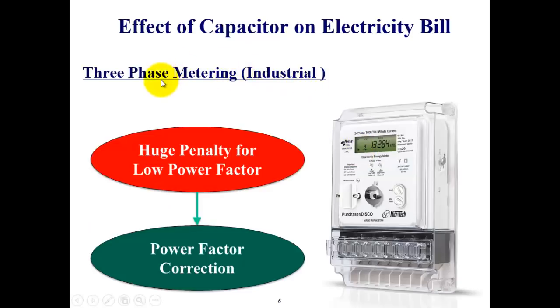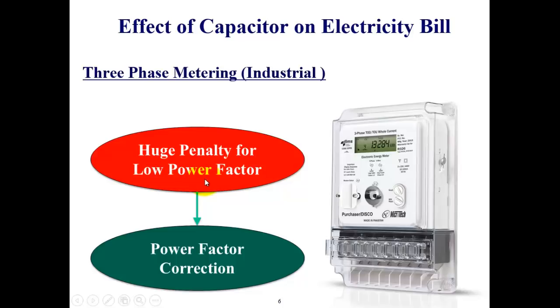Now let's talk about industrial tariff. In industries, we deal with hundreds of thousands of amperes. If the power factor is very low, the industry draws hundreds of extra amperes from the utility, which limits the capacity of distribution equipment. That is why the service provider imposes huge penalties if the power factor falls below the recommended value. To avoid this, capacitors are installed across the supply — this is called power factor correction. By improving the power factor, the consumer avoids penalties and is only charged for the energy they consume, so in industrial tariff, installing capacitors can definitely help reduce the electricity bill.